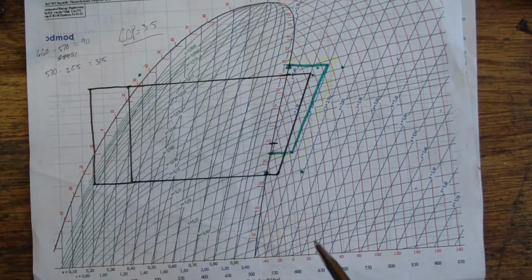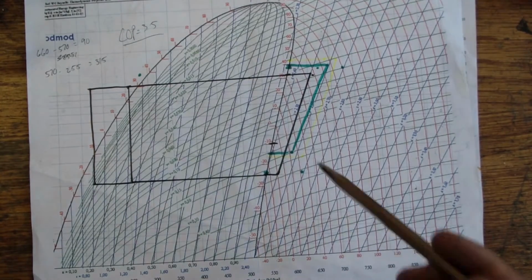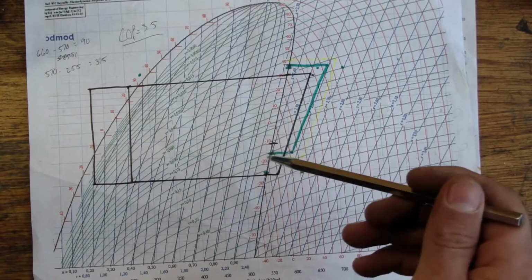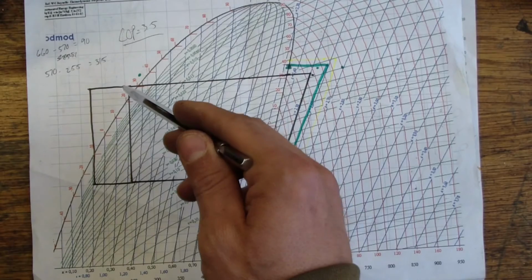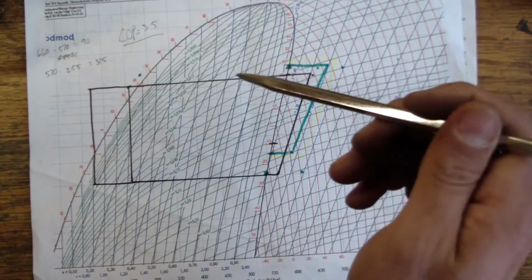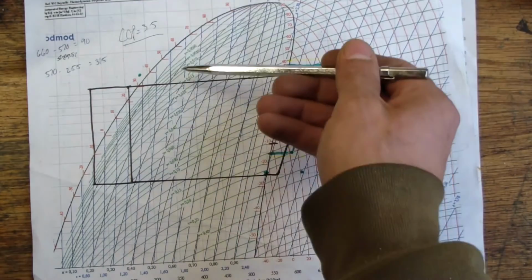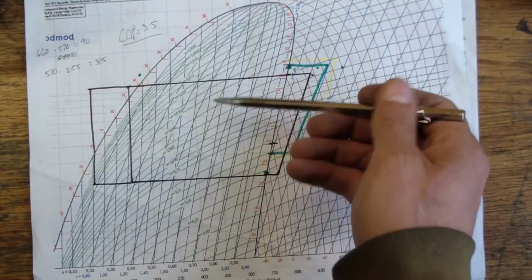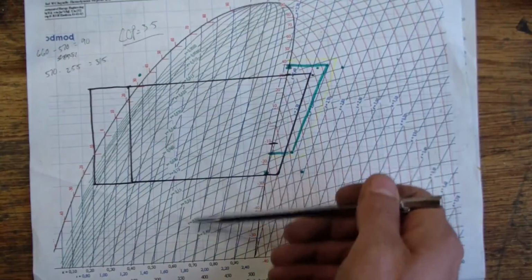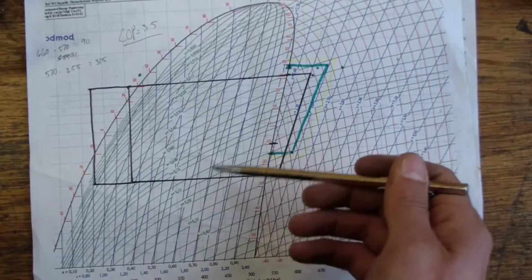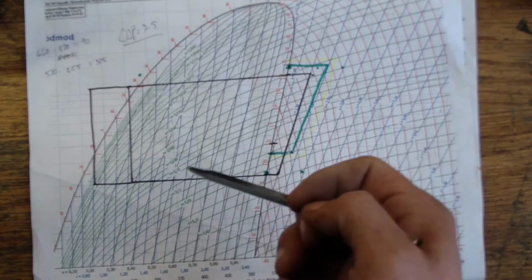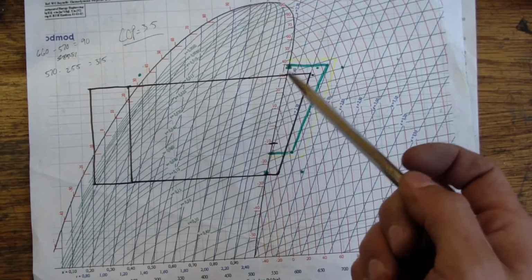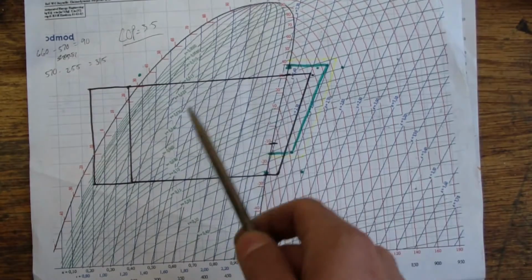So why can this be useful? Well, apart from just kind of visualizing it here, we can look at certain characteristics. So for instance, the first thing that we should really look at is the difference in temperature and pressure between the high side and the low side. The larger the pressure differential and temperature differential between the high side and low side, generally the lower your overall coefficient of performance is going to be. The more work the compressor is going to have to do. And we can look at that in a couple of different ways.